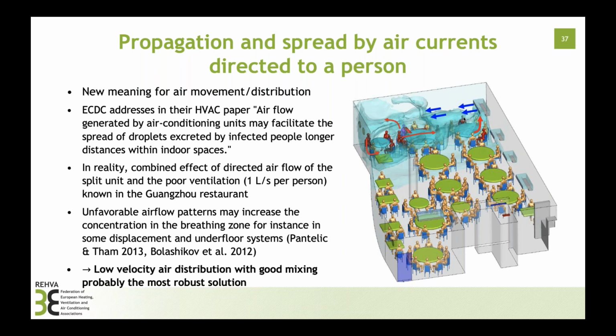So it was suspected that this propagated the spread of the virus. But when it was measured, what was the ventilation in this space? Actually, there was no ventilation. Somewhere here was a toilet, and only a small exhaust from the toilet was the only ventilation. It was measured to be as low as 1 liter per second per person. So it can be said that the main issue in this space was the lack of outdoor ventilation, and the strong directed airflow was a kind of second issue. But indeed, it's safe to apply low velocity air distribution with good mixing. So it's probably the most robust solution. And we have provided in our guidance a limit value for the velocity, 0.3 meter per second, to be sure that this type of directed airflow cannot have an effect on virus propagation.